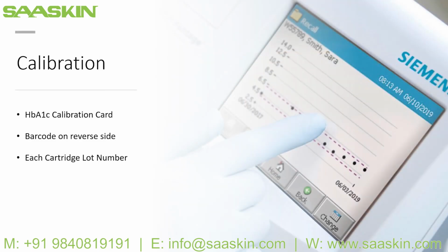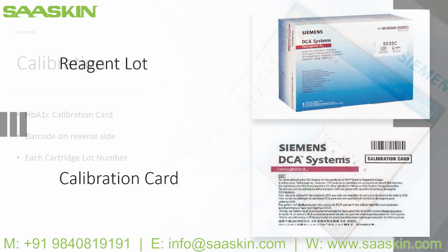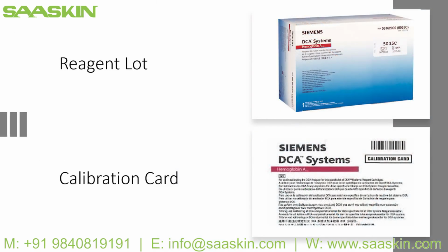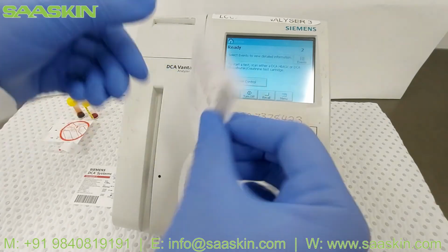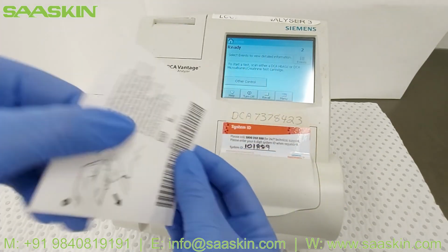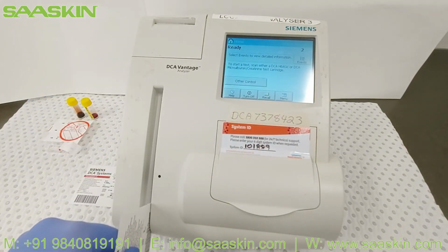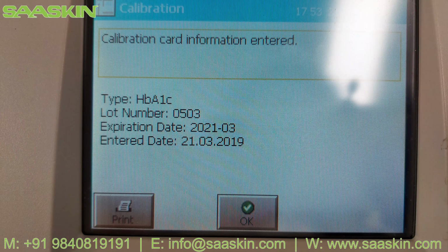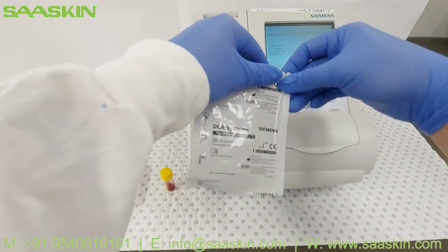The DCA Vantage system is calibrated every time the calibration card is scanned. Scan the calibration barcode before using the reagent cartridges, as each calibration is for a different lot. Now let's get started on sample analysis. Scan the HbA1c calibration card rear barcode from top to bottom past the dot on the onboard barcode reader. An audible beep and notification will appear on the display screen after a successful scan, and press OK to accept.